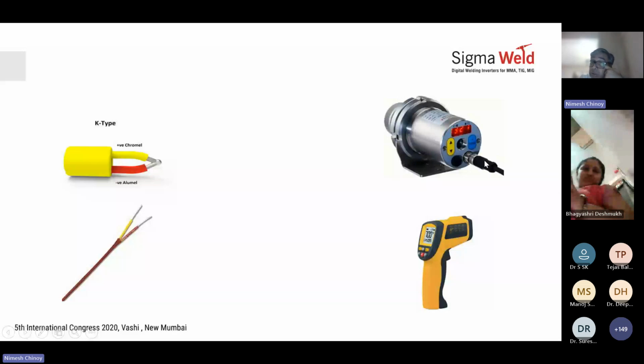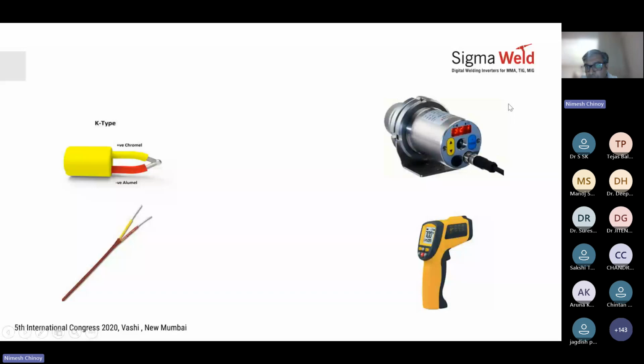Optical pyrometers also come with settings for emissivity because they can differentiate the temperature based on the emissivity of the part. So sometimes it can give you a slightly false reading. So you have to set the mode and the emissivity to give you clear recordings. Then there are handheld temperature guns. Again, these will give you instant readings, but they may not be able to transmit the data to an automation system. So these are handheld devices. These are the ones that relay it and can be captured by an automation system.